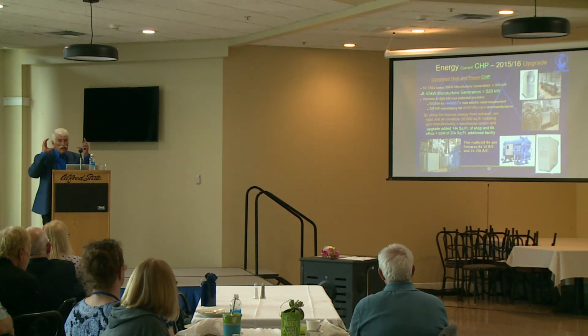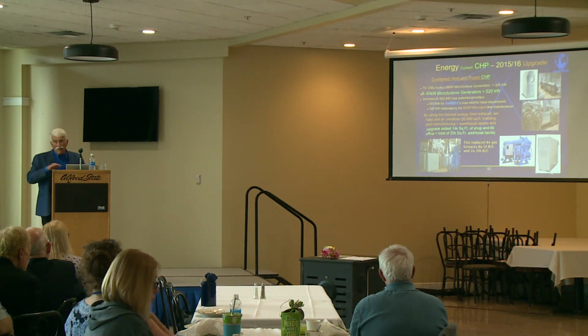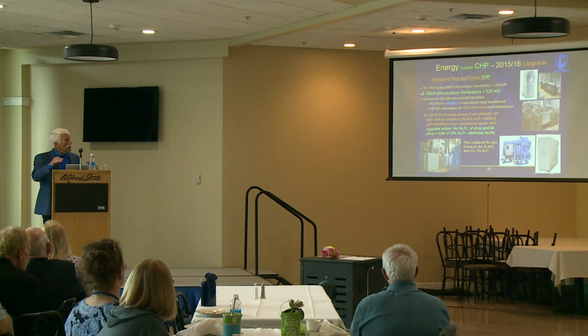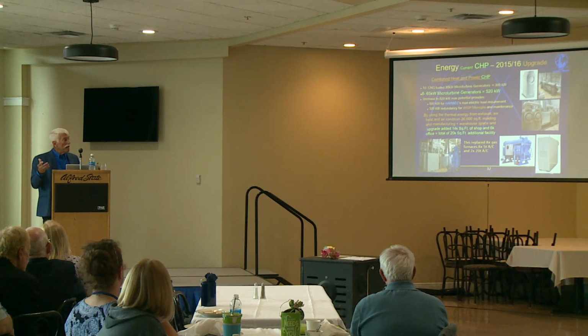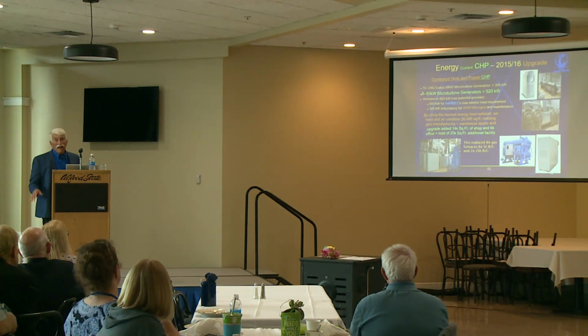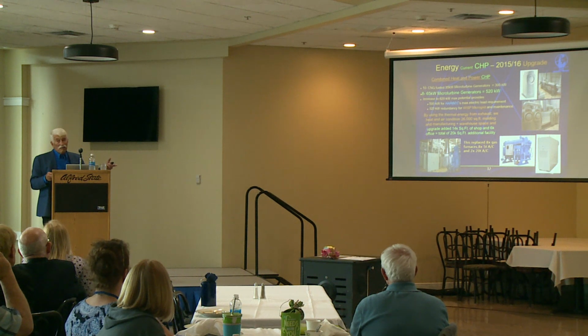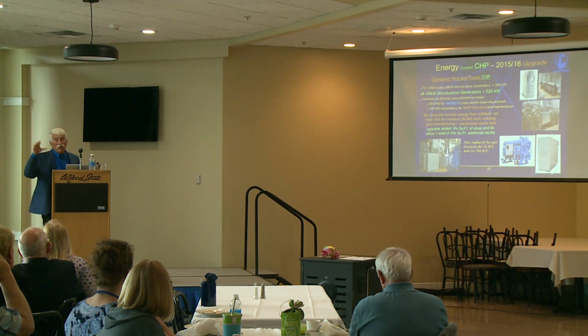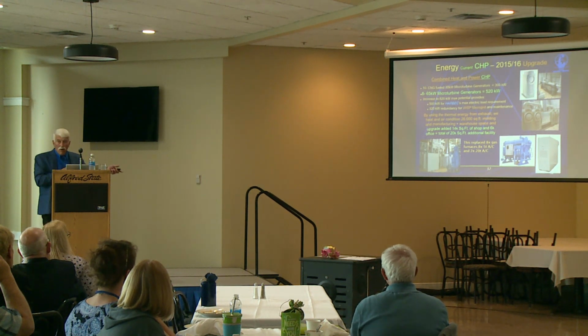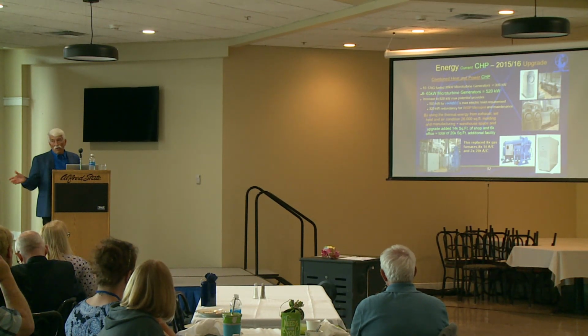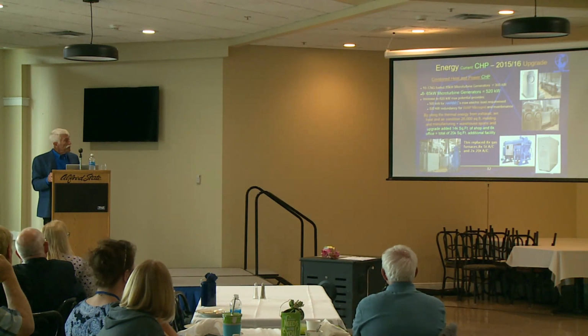We used heavily insulated pipes to capture all the heat we could into that box, a tortuous path of baffles with hot water running through them, and when it came out, we created a constant supply of 200 to 210 degree hot water to do all the heating. All of our floors have radiant in-floor heating. In the old parts of the building where we couldn't tear up the floor, we went back to hanging heat exchangers and just blow the air across the hot or cold coils, producing warm water in the winter for heating and cold water in the summer for air conditioning.